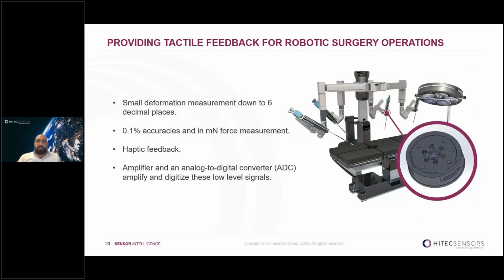Using strain gauge-based sensors allows measurement of slight deformation down to 6 decimal places. With forces applied, these small displacements from load cells, when integrated into surgical tools, are converted into real-time forces and moments, measuring down to 0.1% accuracy and millinewton force measurements.